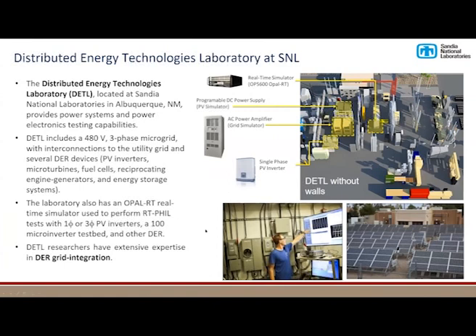We conducted the experiment at DETL, the Distributed Energy Technologies Laboratory at Sandia here. DETL is a highly reconfigurable laboratory with about 150 kilowatts of PV coming into, I'd say, probably a dozen different inverters, and we can hook up different things to either PV simulators, grid simulators, different load banks, create single phase and three phase microgrids, and do a whole host of other experiments. But in this case, we were using a programmable DC power supply, which is our PV simulator, to create a highly variable irradiance profile, and our AC grid simulator, an Ametek simulator, that was connected to the OPAL-RT to provide that hardware-in-the-loop feedback.